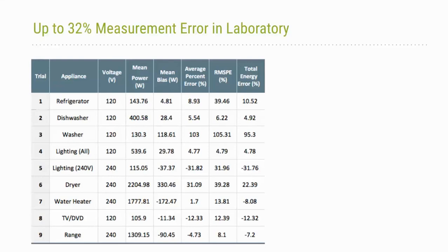We actually hit the highest error measurement for the 240-volt lighting, because these are LED lighting with very small currents. These sensors are self-powered, so they need some current going through the cable to work. With very low currents, they may measure zero even though there's definitely some current along the wire—just to give you an idea of how this technology behaves.